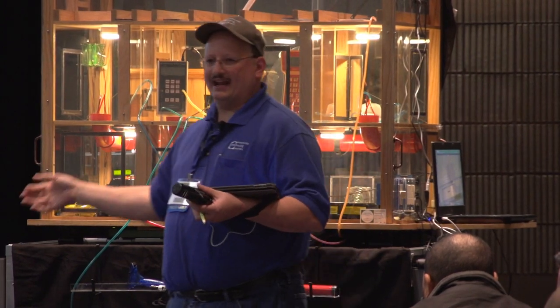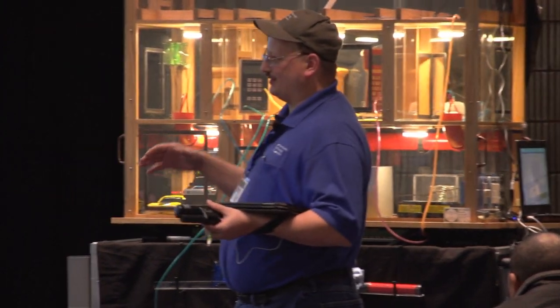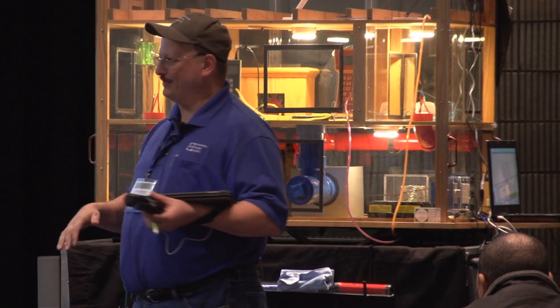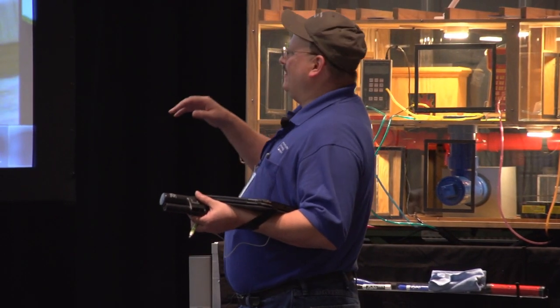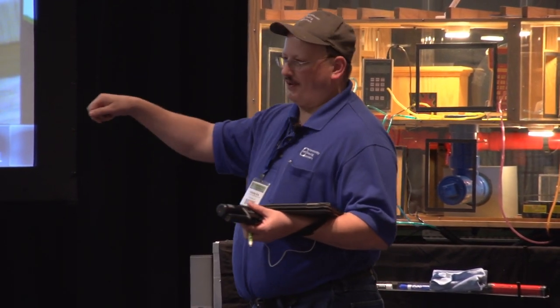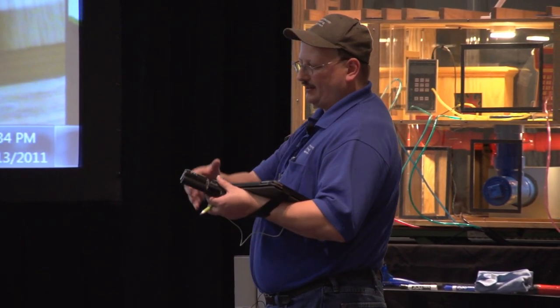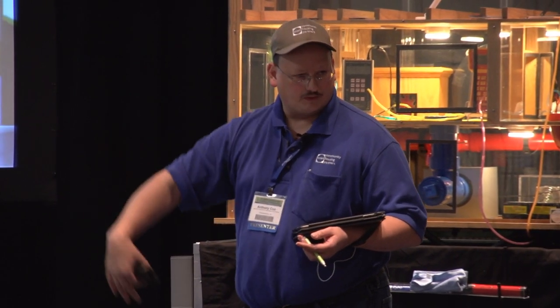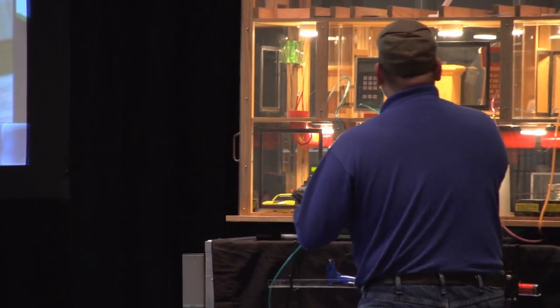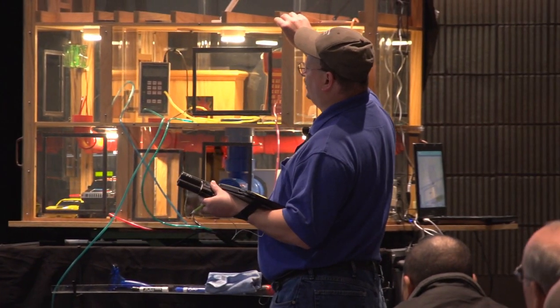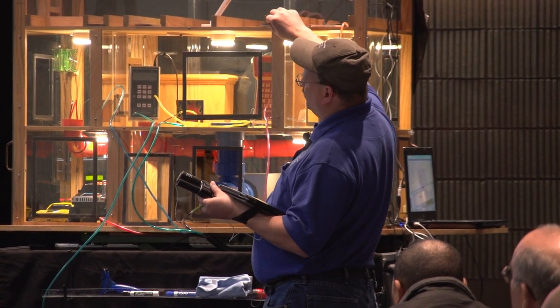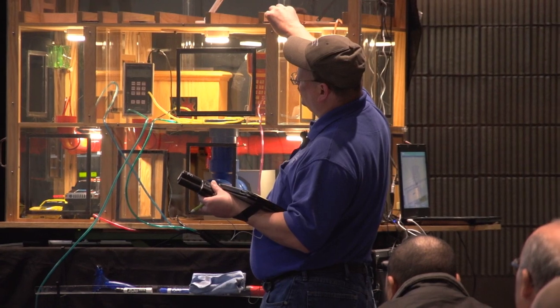So if you're in the attic, if you trust your buddy you're with to lock you up in the attic while you're running the blower door, as long as they let you out, right? Then you can go through the attic with the smoke pencil anywhere you think there are leaks and check. And if it's a leak, it's going to do what? Pull it down. And what about after the work? What about after the work if I seal it? I got a little clear piece here. I'm going to seal this.